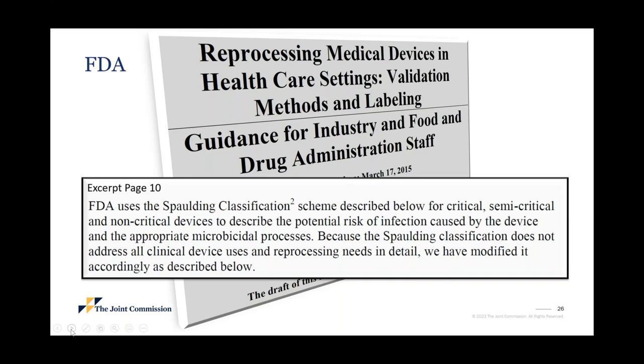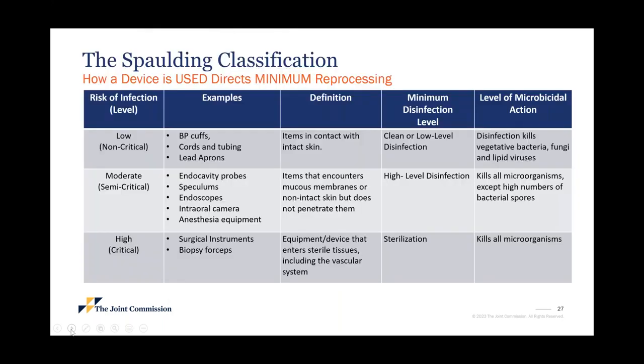The important part here is, what does the FDA expect manufacturers of these medical devices to do as far as reprocessing? They are very clear that manufacturers must follow the Spaulding classification, meaning is it critical, semi-critical, or non-critical, and is it being reprocessed accordingly? This is an example of the Spaulding classification, and it tells users the minimum level of reprocessing that must be required when an instrument is used.